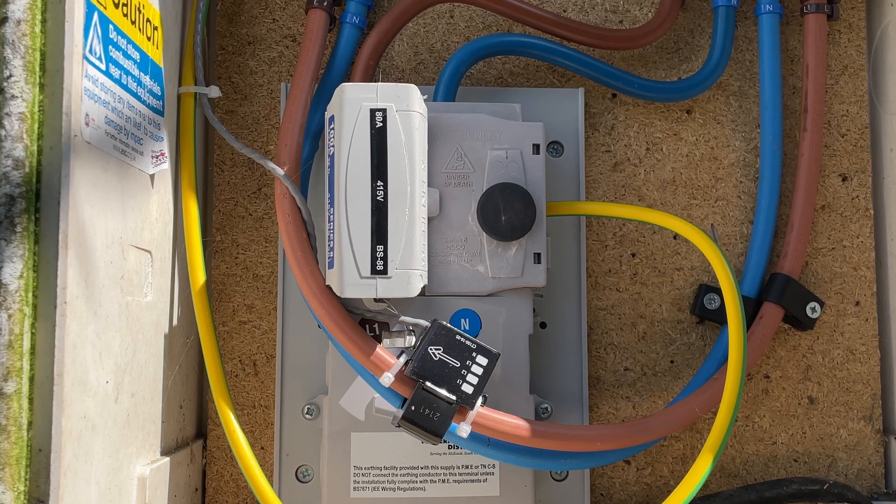The CT clamp relays this information down a wire to your Eddi — you can see the wire there, it's the grey one wrapped around the brown cable; it's a bit like an ethernet cable. The genius of the Eddi is that it uses this information and takes whatever surplus power you're generating and diverts it to your immersion heater. If you only have a small surplus, it will heat the water up slowly, but if you have a larger surplus, it will take up to three kilowatts — the maximum power of the heater. The net result is hot water for free, unless you count the capital cost of the kit, of course.